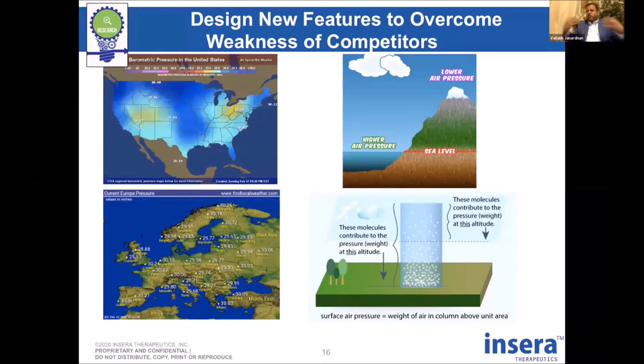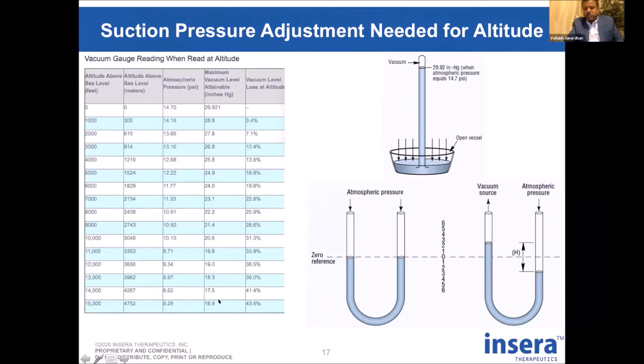If you go to a higher elevation, an analog dial, which most existing systems have, gets frame shifted to account for the weight of the column at that height. So instead of showing -29 inches of mercury, it shows a much lesser, suboptimal maximum suction pressure. For example, at around 8,000 feet elevation, you get about a -7 frame shift, so the dial on the vacuum pump only shows -22. The operator may feel they can only reach -22 inches of mercury instead of -29, which is closer to pure vacuum.